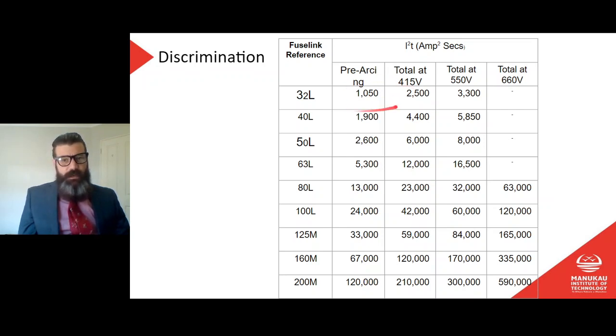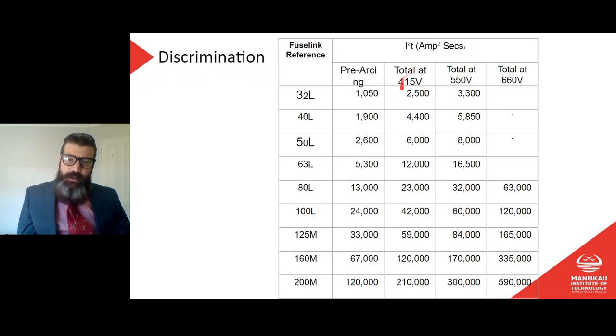So pre-arcing is 1050, total breakdown at 415 volts, so that's our normal three-phase voltage, is 2,500, and then at 550 it's 3,300. It doesn't have a time. If we're at 80 amp, then it's 63,000. Never mind about any of that. So these totals are the maximum amount of energy that fuse will let through before it is completely broken and completely open circuit.